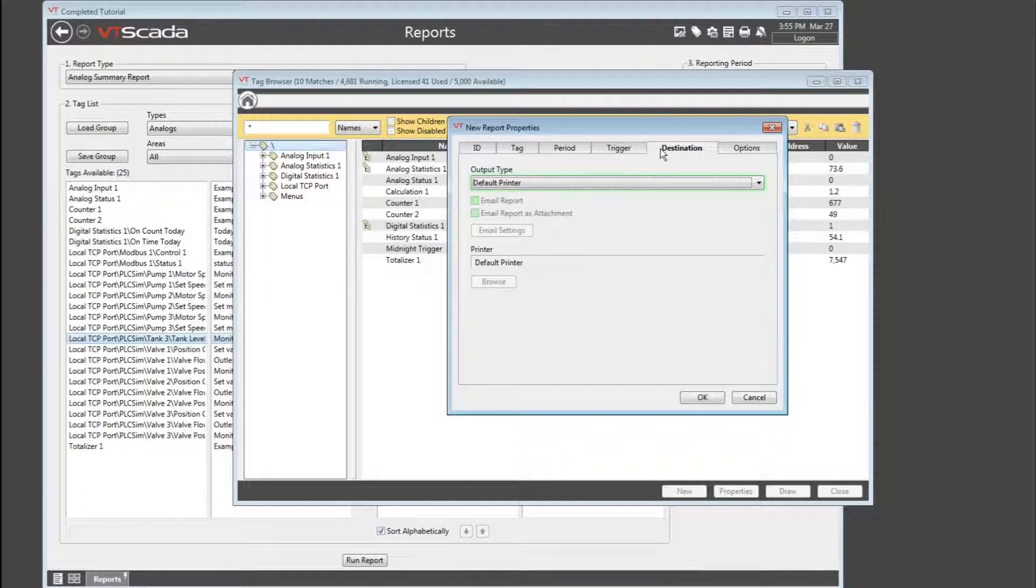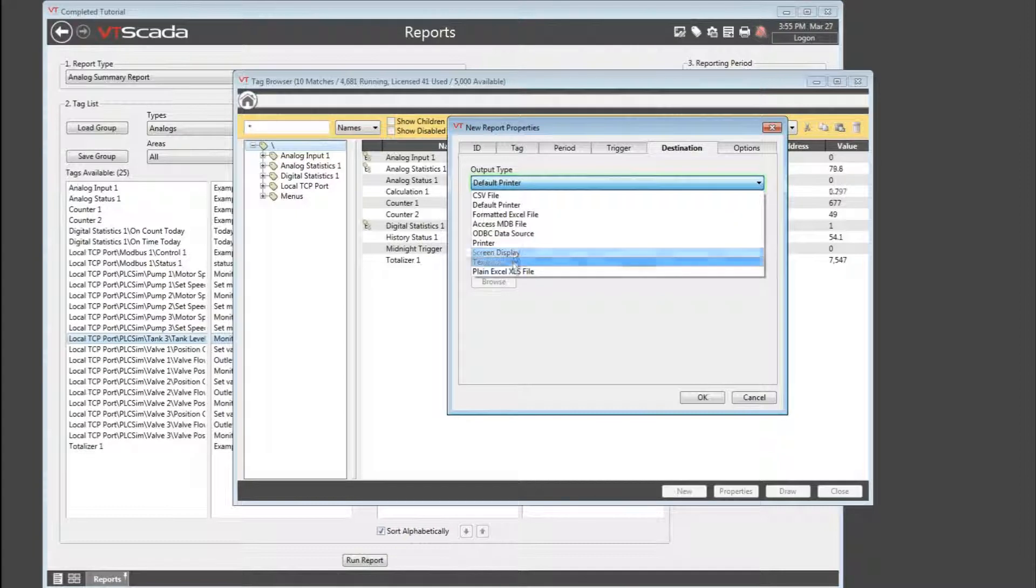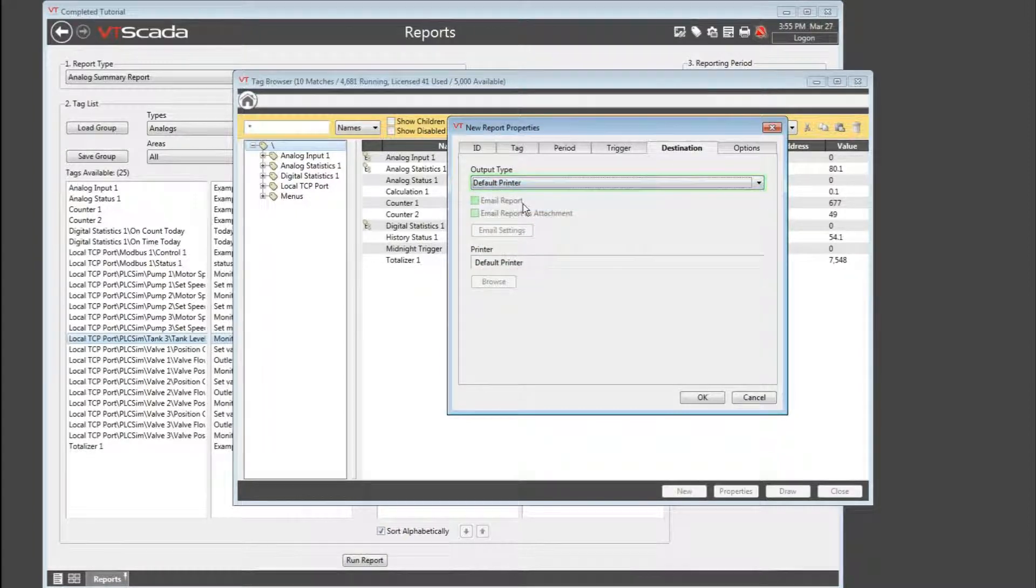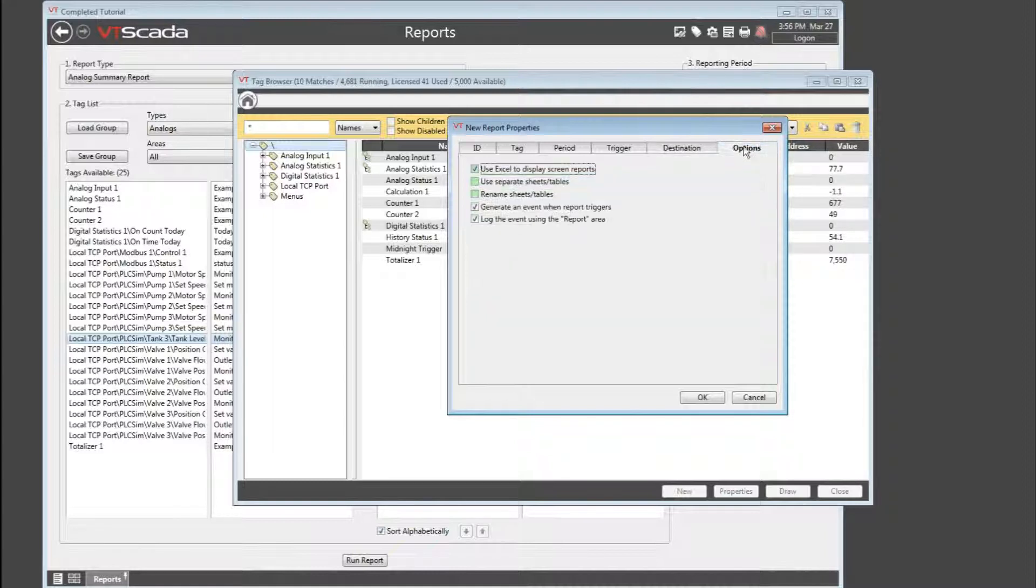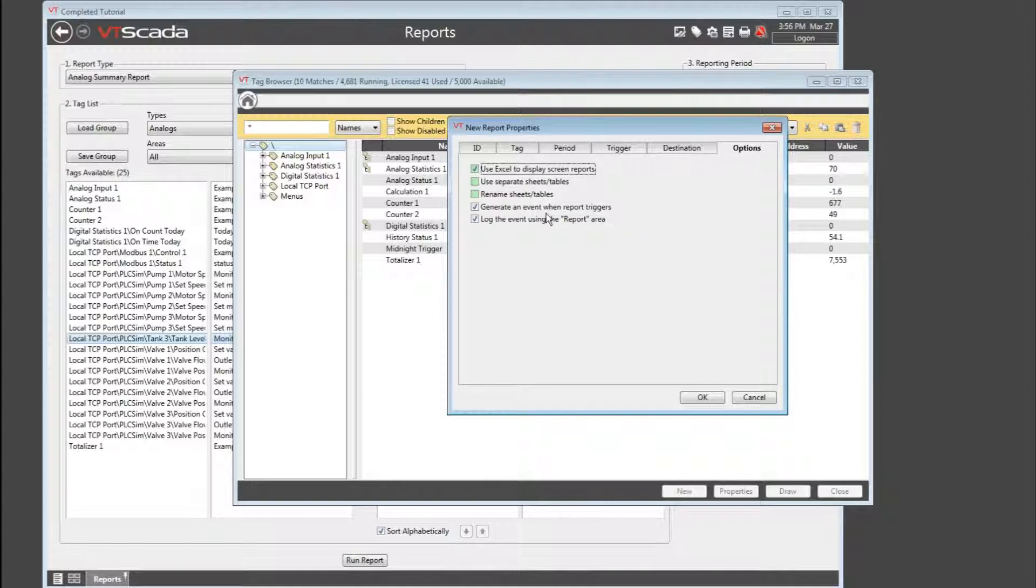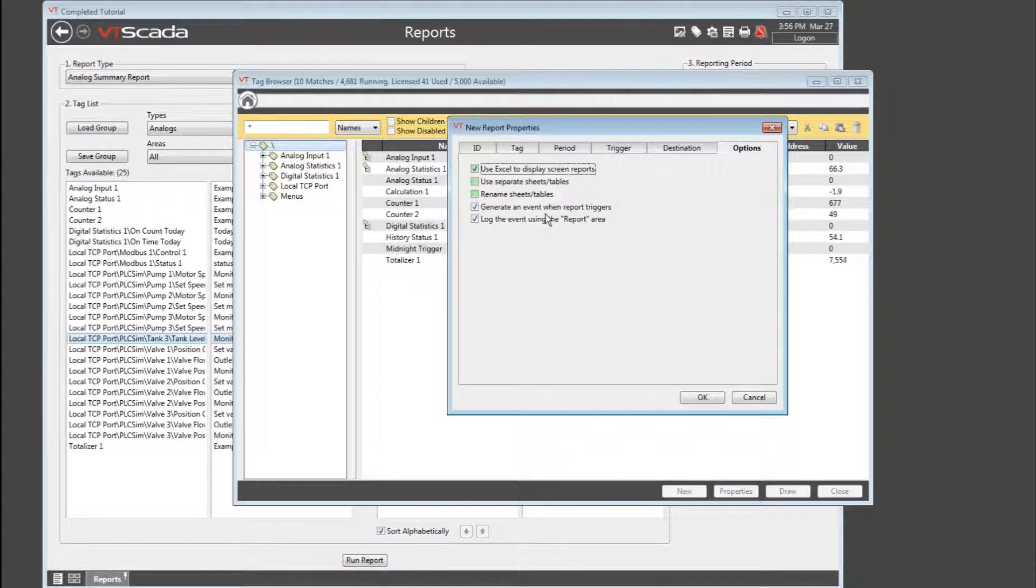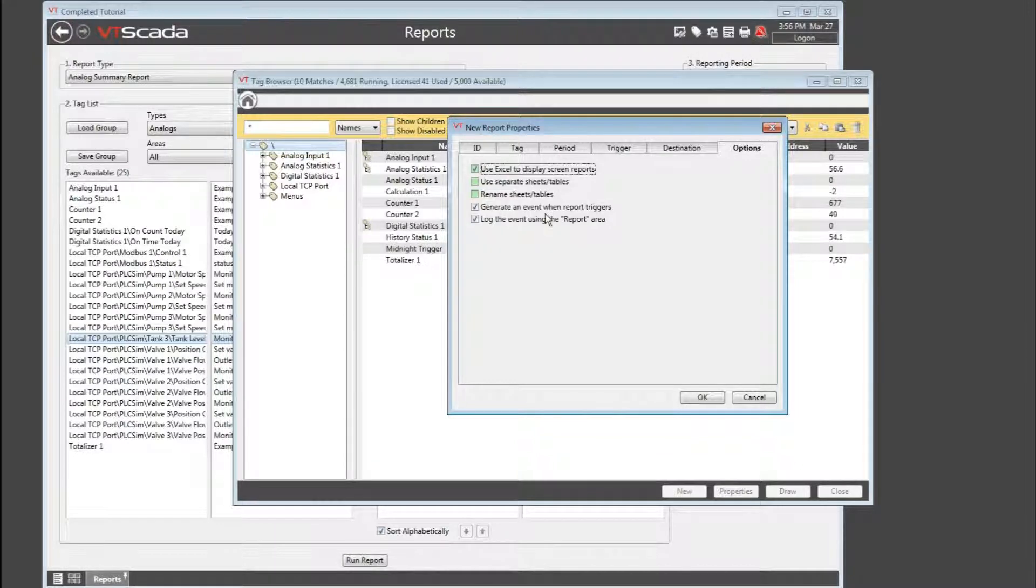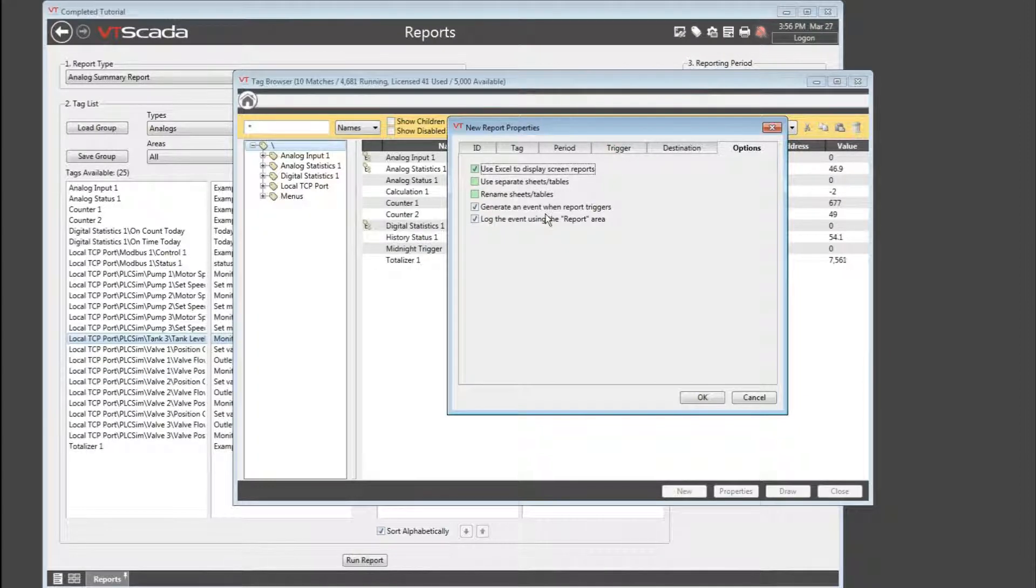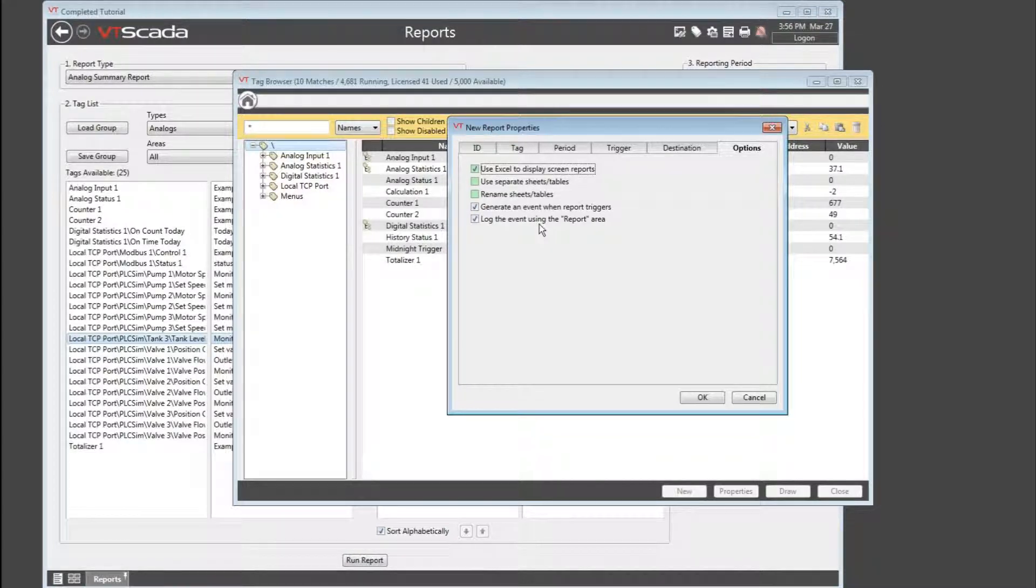The destination is much the same as it was before. I can go to a default printer or to a screen display, text file, anything at all. Perhaps I'll leave that as default printer for now. And finally a few options if I were using a screen report. Plus there are two brand new options here that we did not see before. First off, this is going to generate an event in the alarm history when the report triggers. You pretty much always want to leave that one selected. It'll also log that event using the report area name.